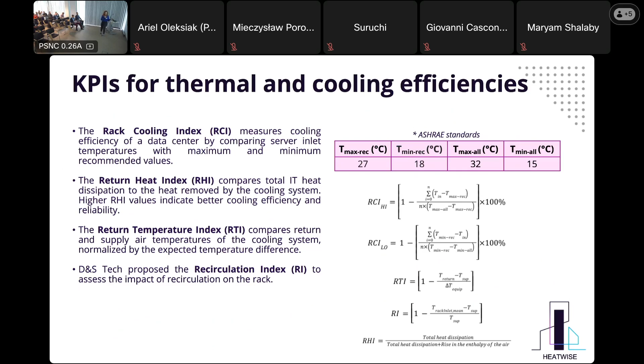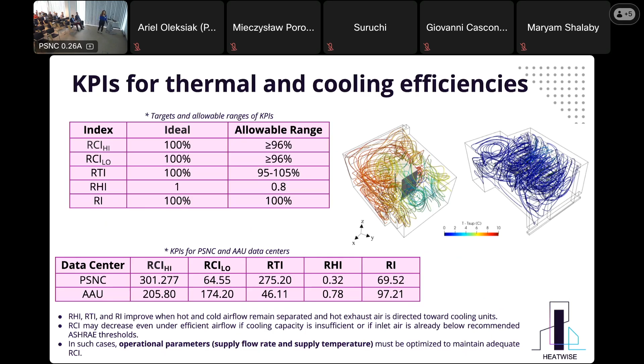We improved them in communication with the partners by introducing some retrofit ideas. We especially increased RHI and RI, and the RTI is a little bit higher than we desired. RHI, RTI, and RI improve when hot and cold airflow remain separated and hot exhaust air is directed toward cooling units. RCI may decrease even under efficient airflow if cooling capacity is insufficient or if inlet air is already below recommended ASHRAE thresholds. In such cases, operational parameters, supply flow rate, and supply temperature must be optimized to maintain adequate RCI.